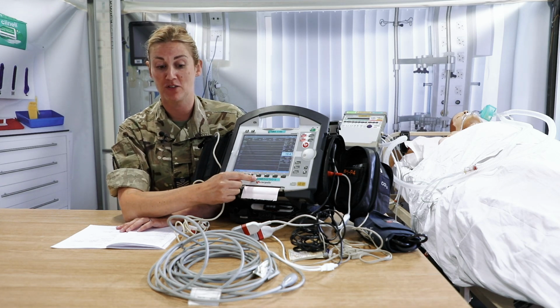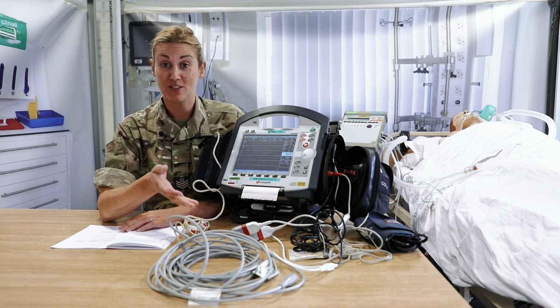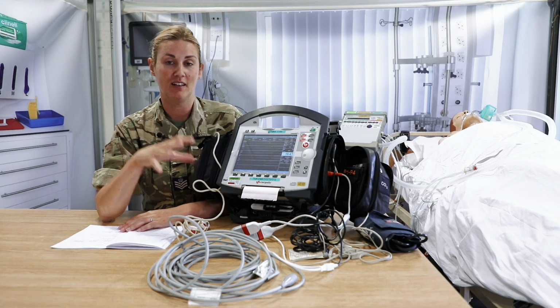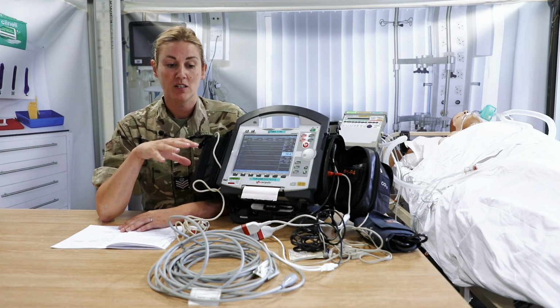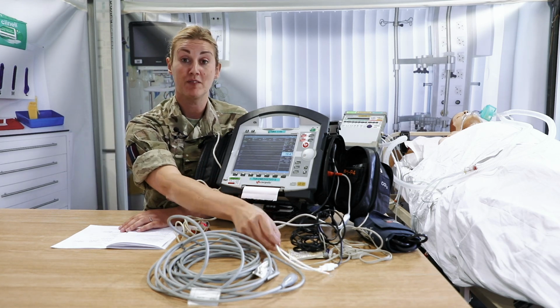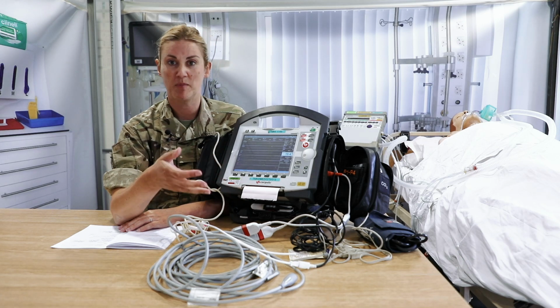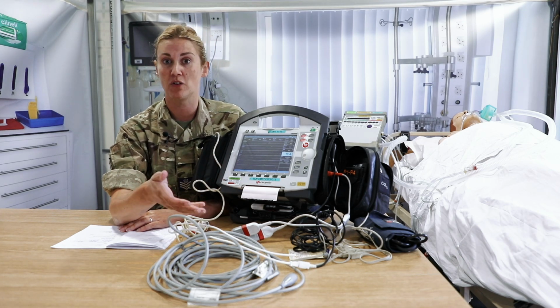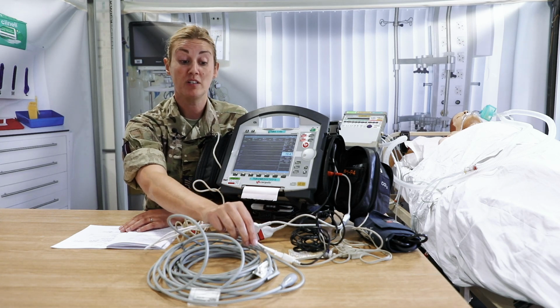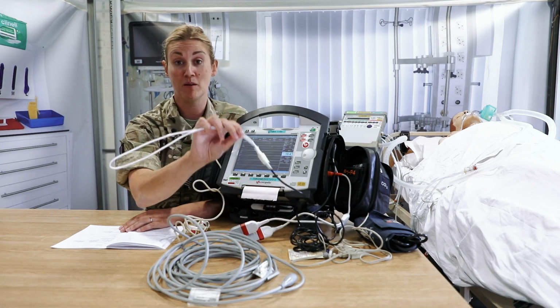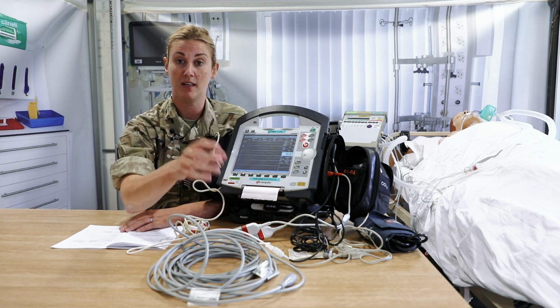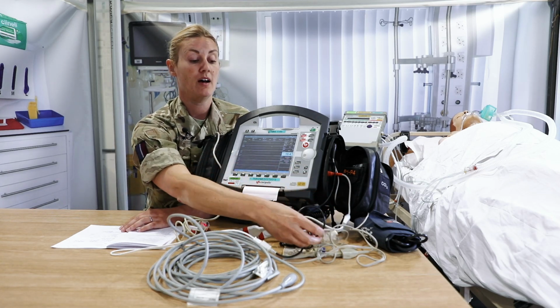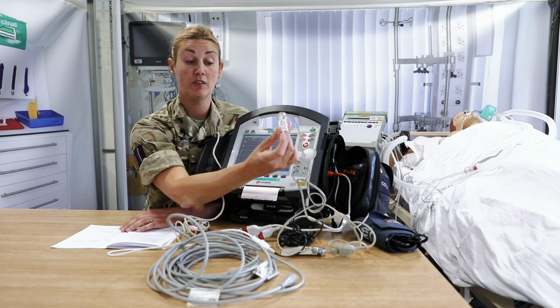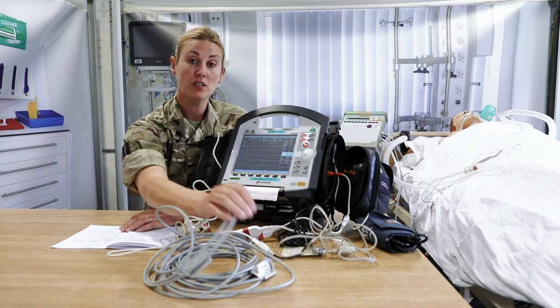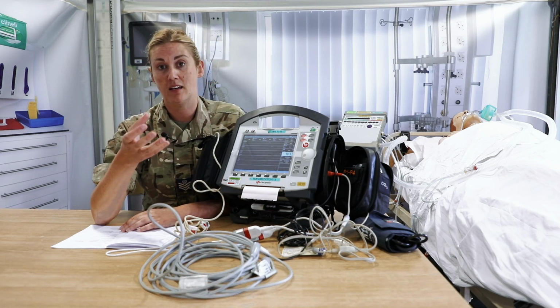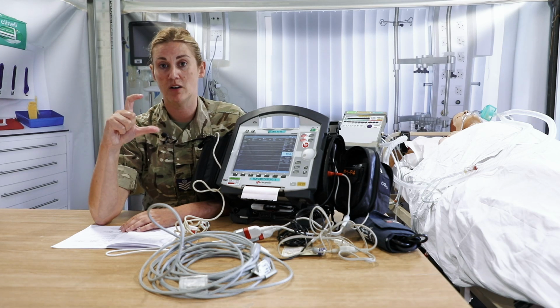Once we've been through the defibrillator, we're going to make our way through the rest of the buttons to confirm their functionality. You'll see that I've got a lot of the leads already out, because we're going to actually check that the leads work and do what they're supposed to do. So it's really helpful to make sure that you have some dummy kit to do this, and we'd recommend putting a little 373 pack together so that you can perform these tests. So your dummy kit should include a dummy temperature probe, either the invasive or the sticky dot is fine. You should have dummy end-tidal CO2 cuvettes. And also, to test your invasive leads, you can just take a transducer and literally just cut out the transducer section.